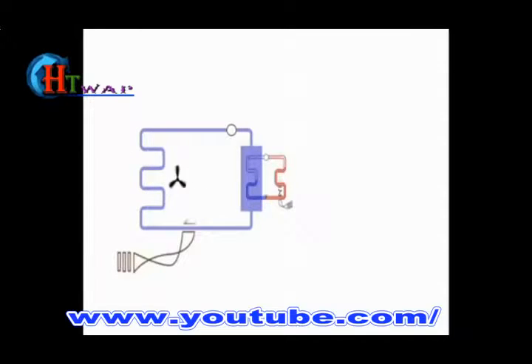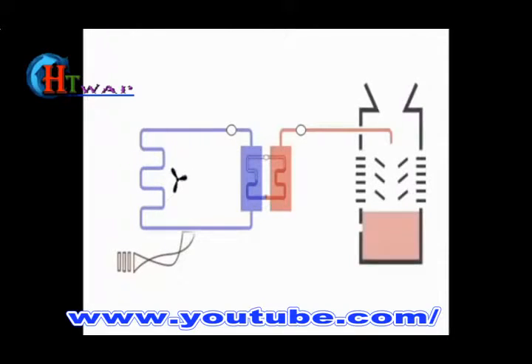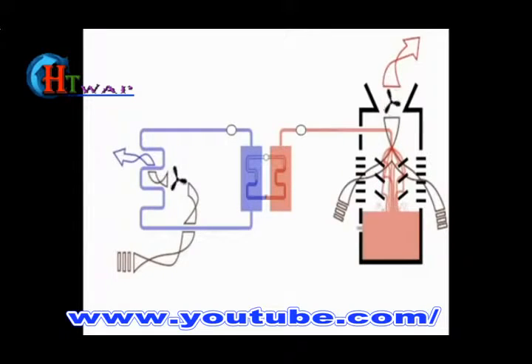Similarly, on the hot side, we might increase efficiency and capacity by removing the heat in the condensing coolant with another separate loop of water. This condenser water is pumped from the condenser to a cooling tower, and water is allowed to cascade over a series of baffles, where the water is cooled by the outside air. When needed, an impeller fan can assist airflow across the cascading water. Some of the water evaporates and is replaced with new water, but most of it falls to a pool, where it is pumped back to the condenser.